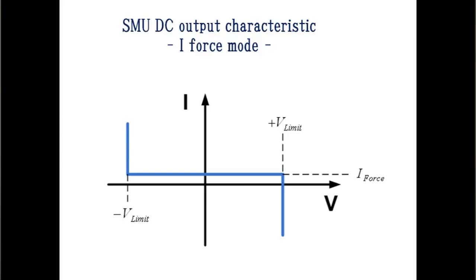Today, I'll use B2911A precision source measure unit. This figure shows DC output characteristic of this SMU when it is set to I force mode. From minus V limit to plus V limit, output current is constant. Force current value can be set to 0mA and this means input resistance value is very high and current flowing into the DUT is very low.